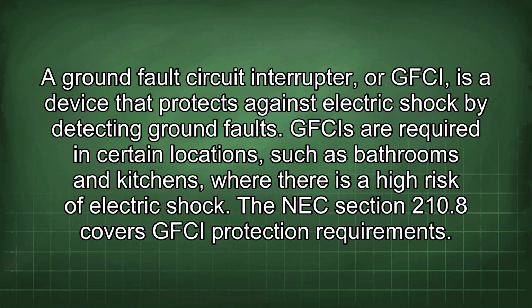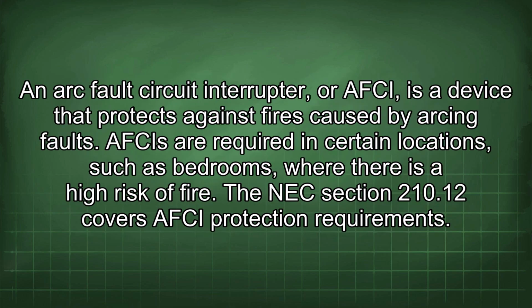A ground fault circuit interrupter, or GFCI, is a device that protects against electric shock by detecting ground faults. GFCIs are required in certain locations, such as bathrooms and kitchens, where there is a high risk of electric shock. The NEC section 210.8 covers GFCI protection requirements. An arc fault circuit interrupter, or AFCI, is a device that protects against fires caused by arcing faults. AFCIs are required in certain locations, such as bedrooms, where there is a high risk of fire. The NEC section 210.12 covers AFCI protection requirements.